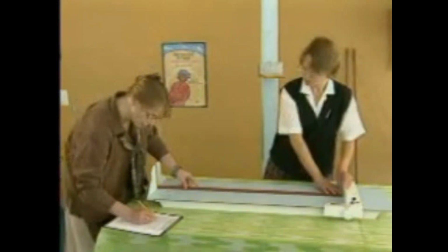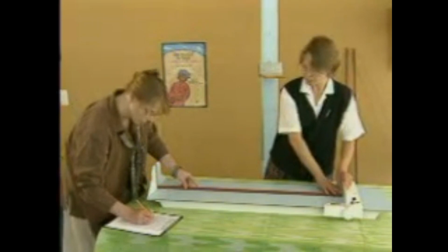Length and height boards: verify accuracy using rods of known lengths, for example, a 50 centimeters rod. The board's reading should match the known measurement exactly. If any equipment is found to be inaccurate, it should be calibrated. If calibration is not feasible, the equipment must be replaced.